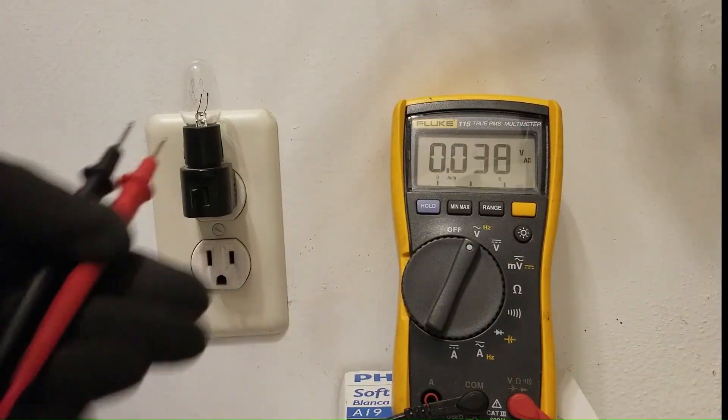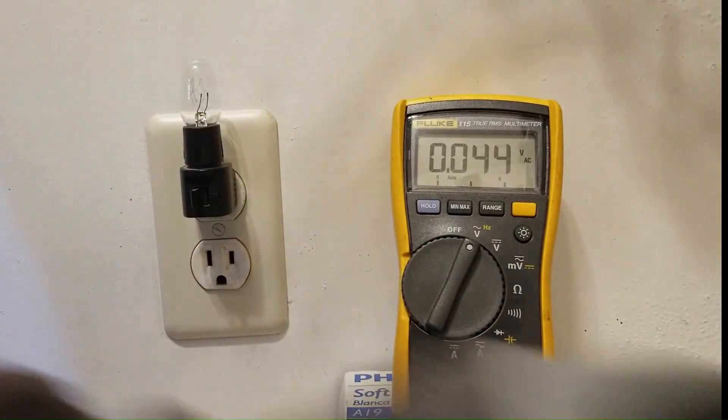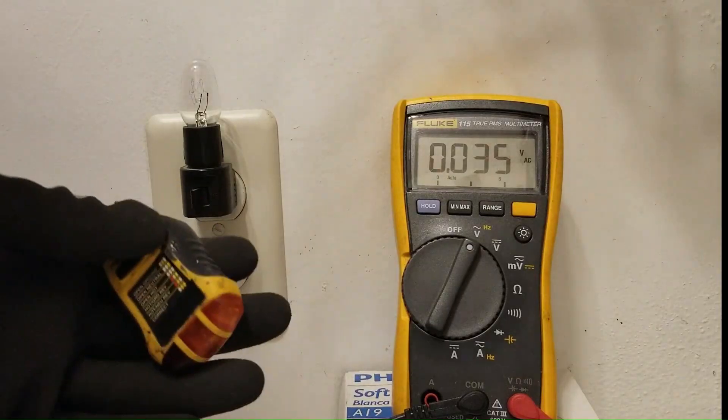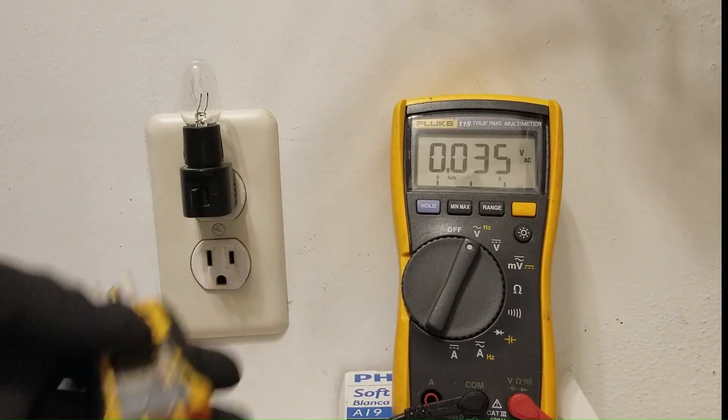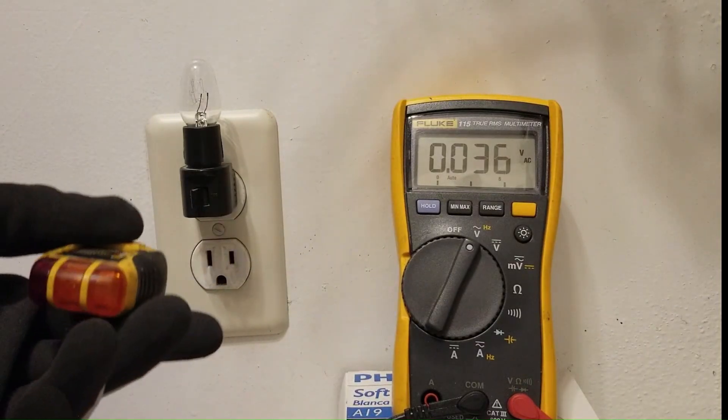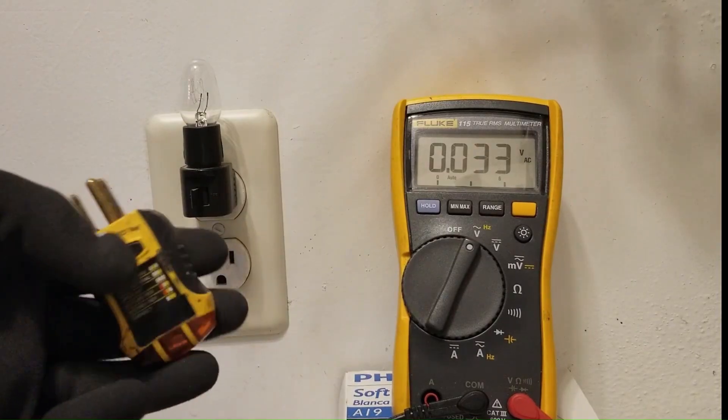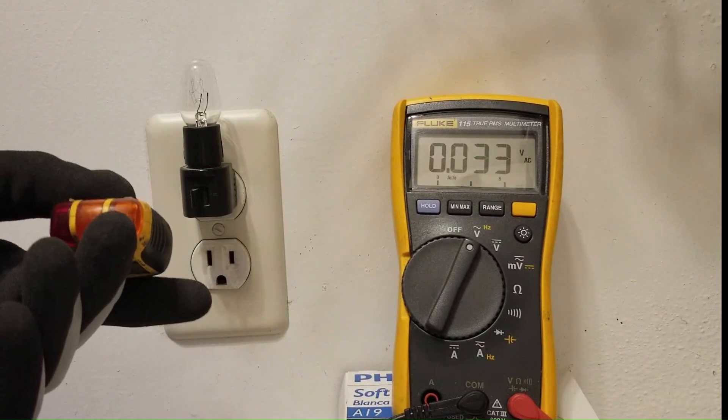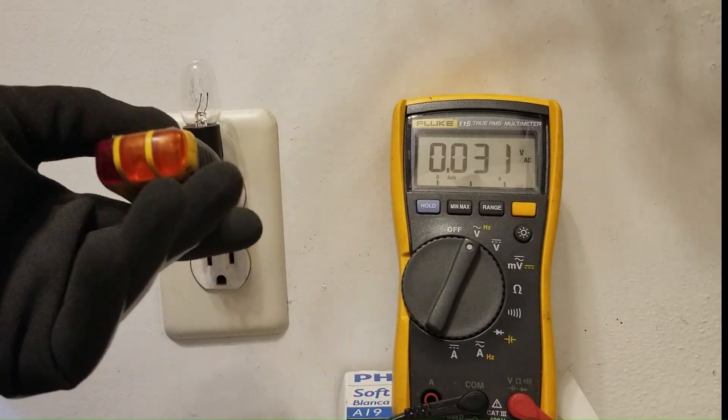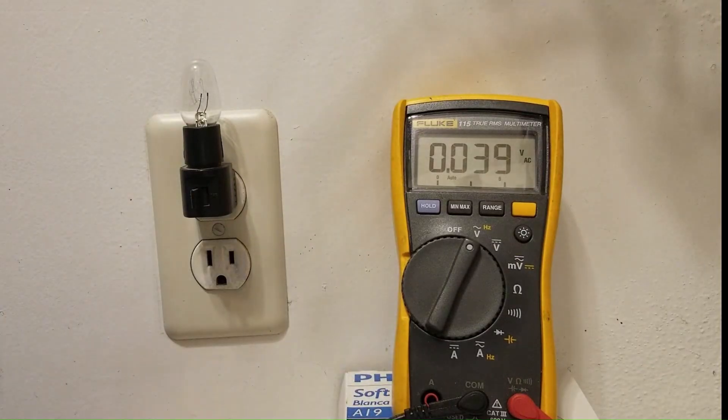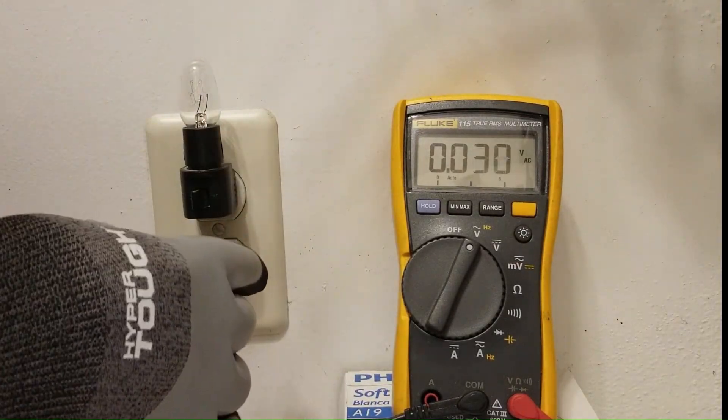So we have a problem with this outlet, even though the voltage tester says it's good. But again, the voltage testers are looking for open lines. And this is not an open line. This is a loose neutral. It's a type of a neutral issue that is a result of an upstream loose connection that causes the outlet to fail under load.